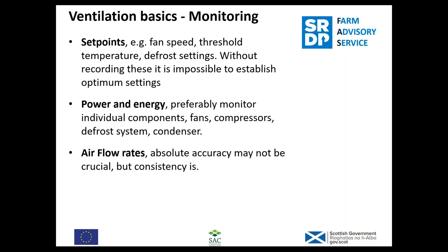Airflow rates: there are many ways of doing it and many points. People get hung up on absolute accuracy, but airflow is a very hard thing to measure. I think the absolute value doesn't really matter — it's got to be consistent, so as you change your fan settings, box settings, or air distribution, it shows that up. I wouldn't go for a very expensive accurate one — that could be ten to twenty thousand pounds. Some simple pitot tubes or impeller systems can tell you a lot.